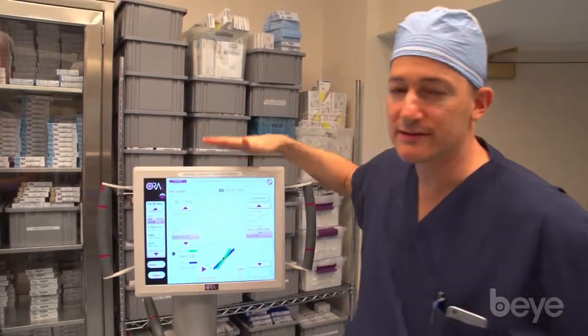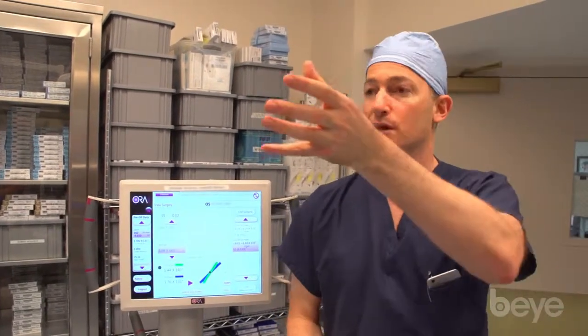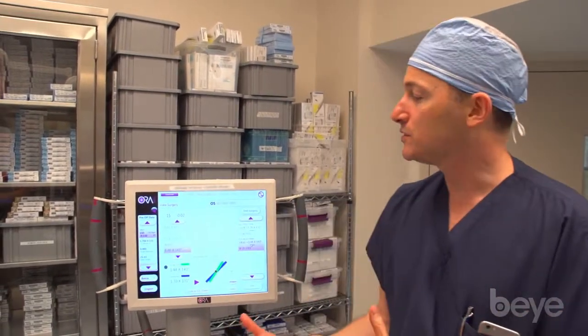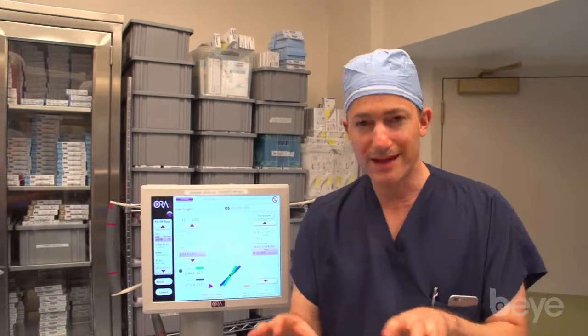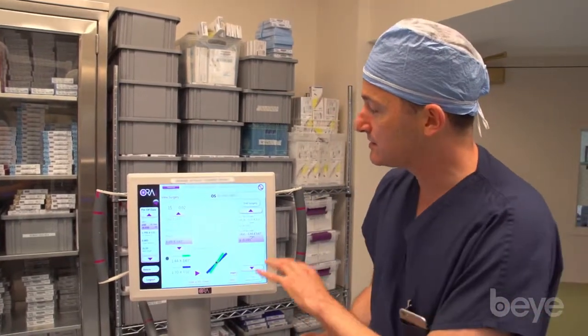As good as the ORA is, there are challenges. It relies on a very clear optical interface — the waveform has to go through the cornea and lens and bounce off the retina. There are times when we're not getting a good measurement, whether it's a speculum, dry eye, or bubbles in the eye. Once you get good at it you're able to get everything in position to get readings — I'd say about 99% of the time. It's not perfect yet, and it's always an evolution.